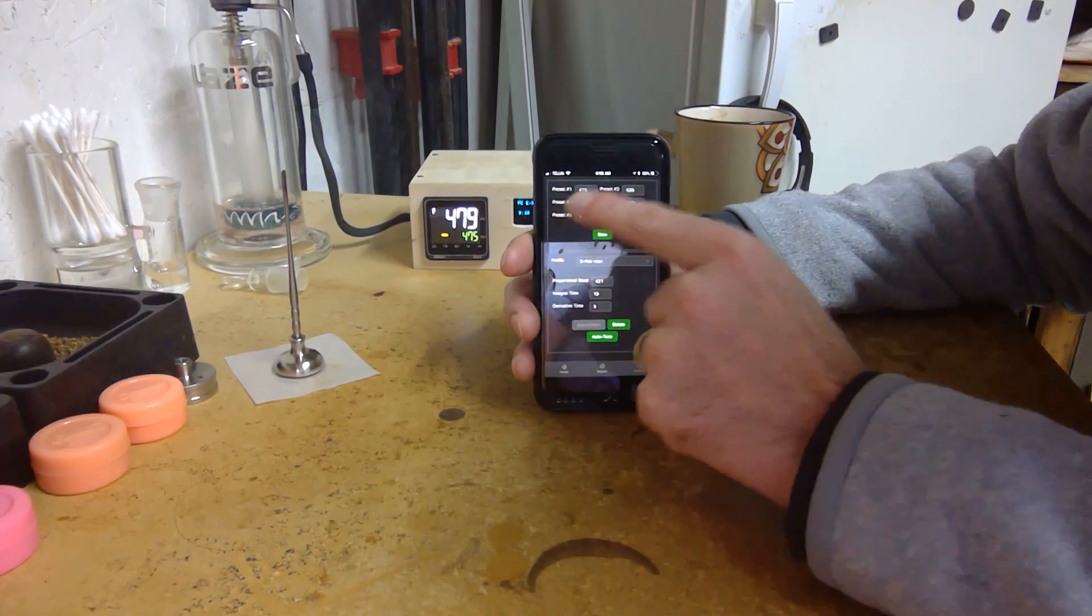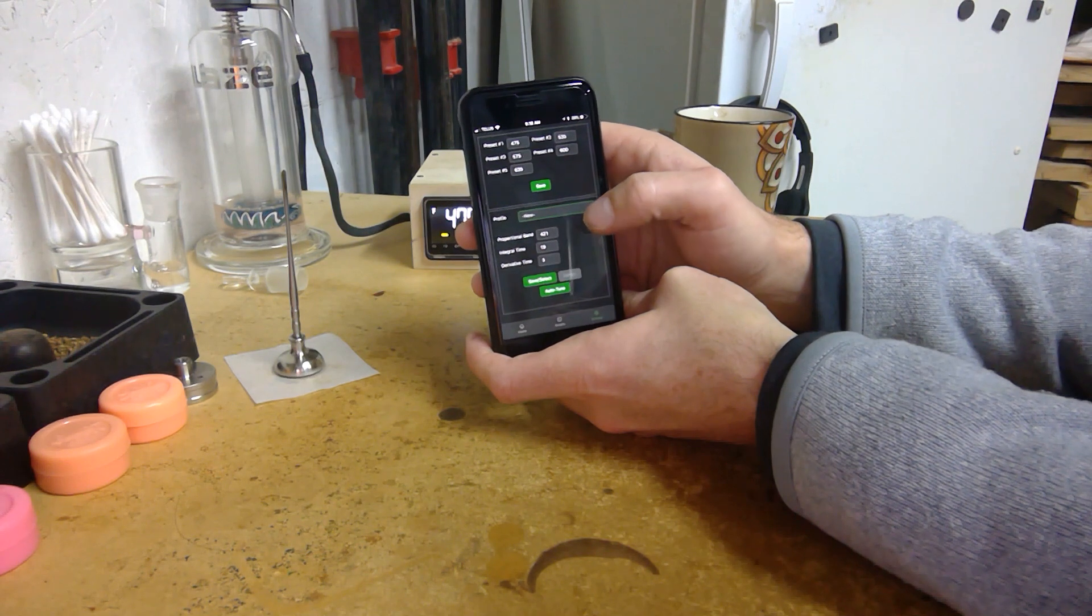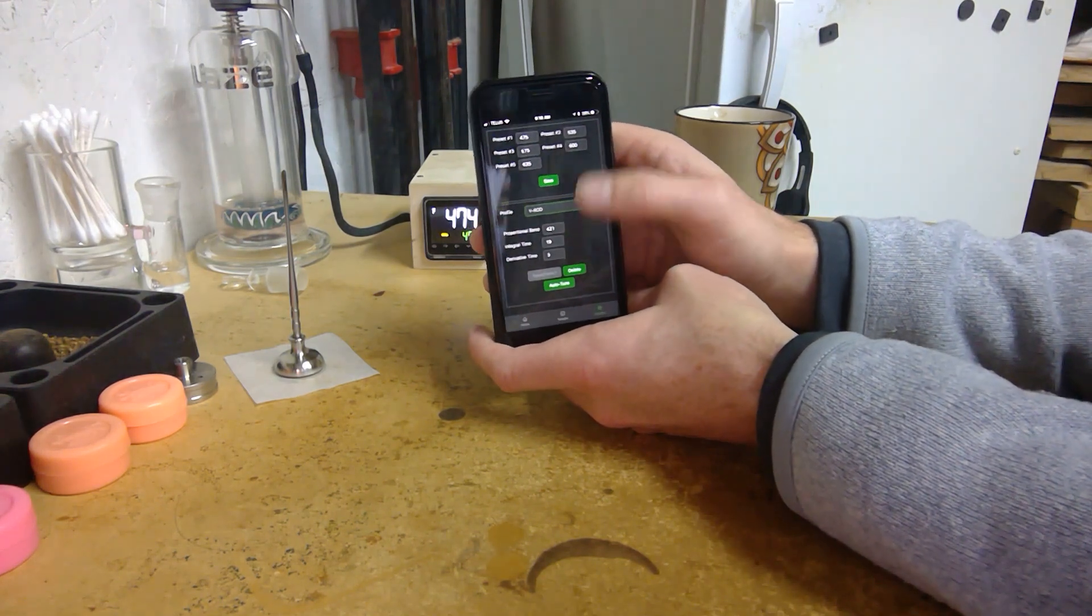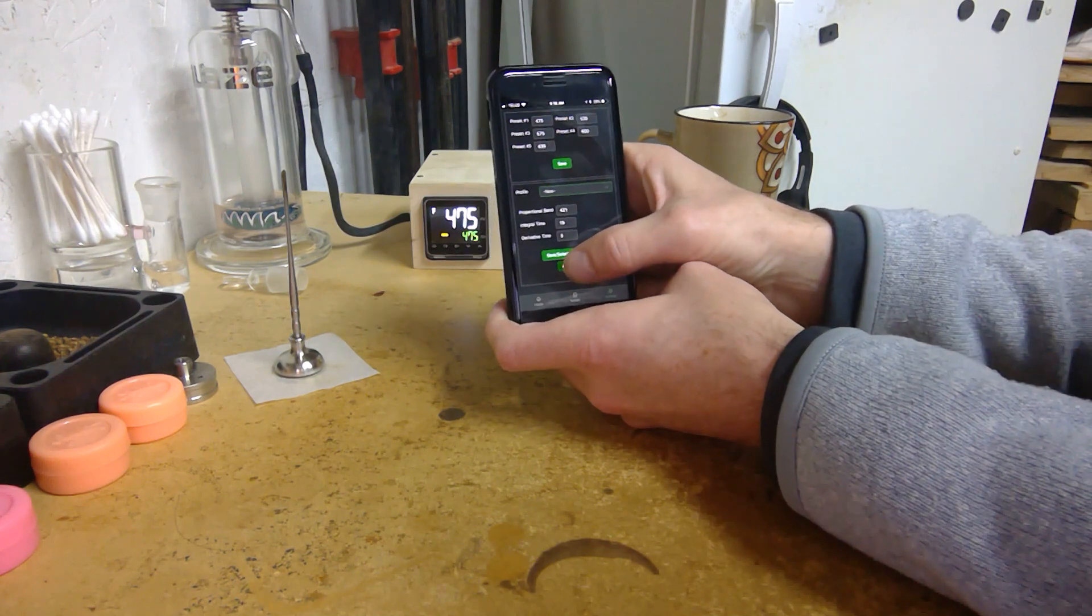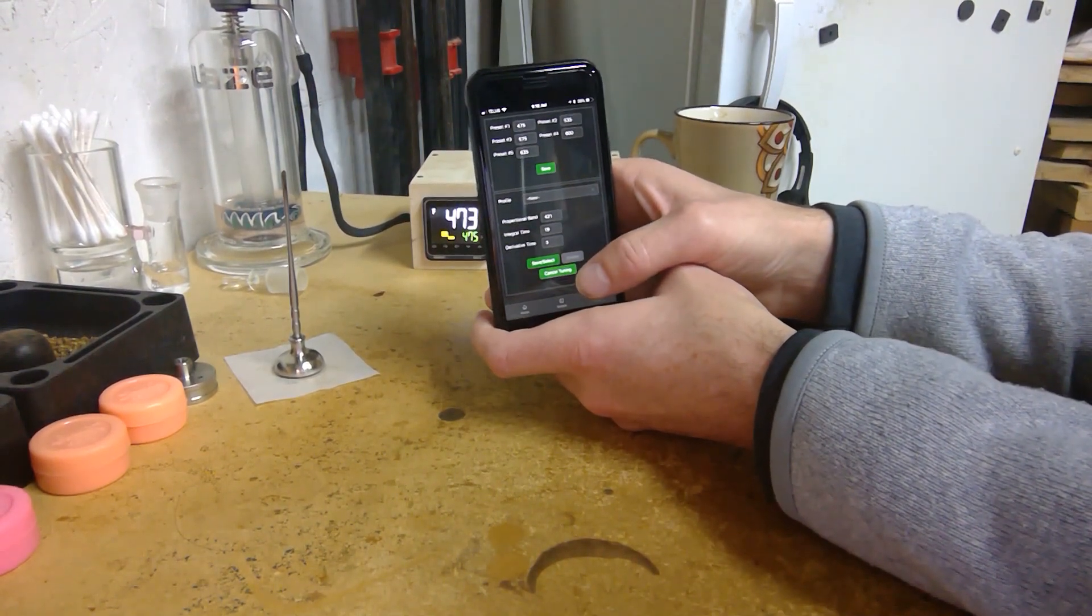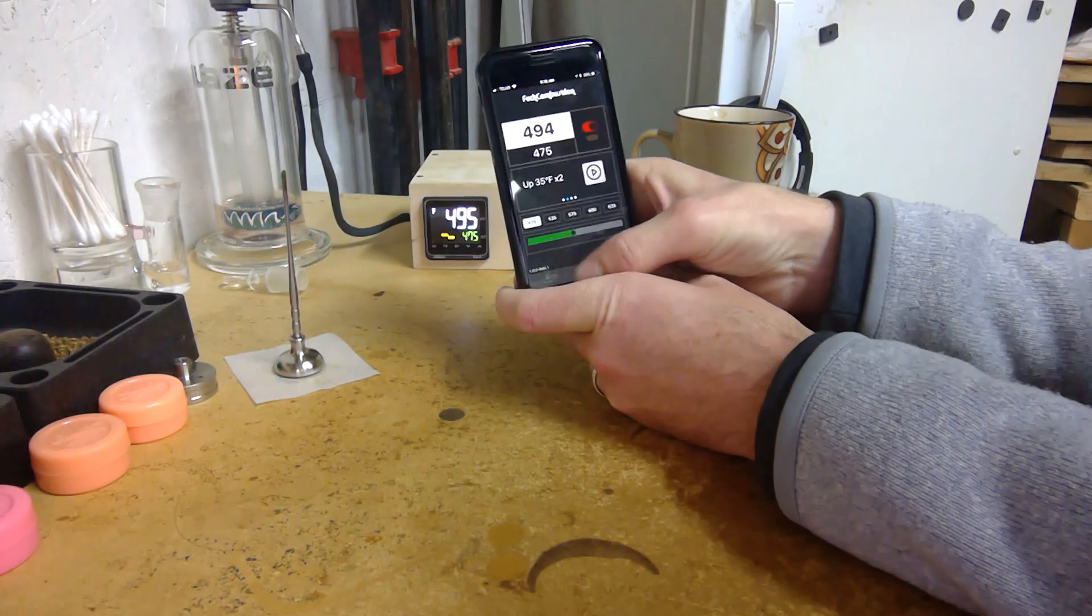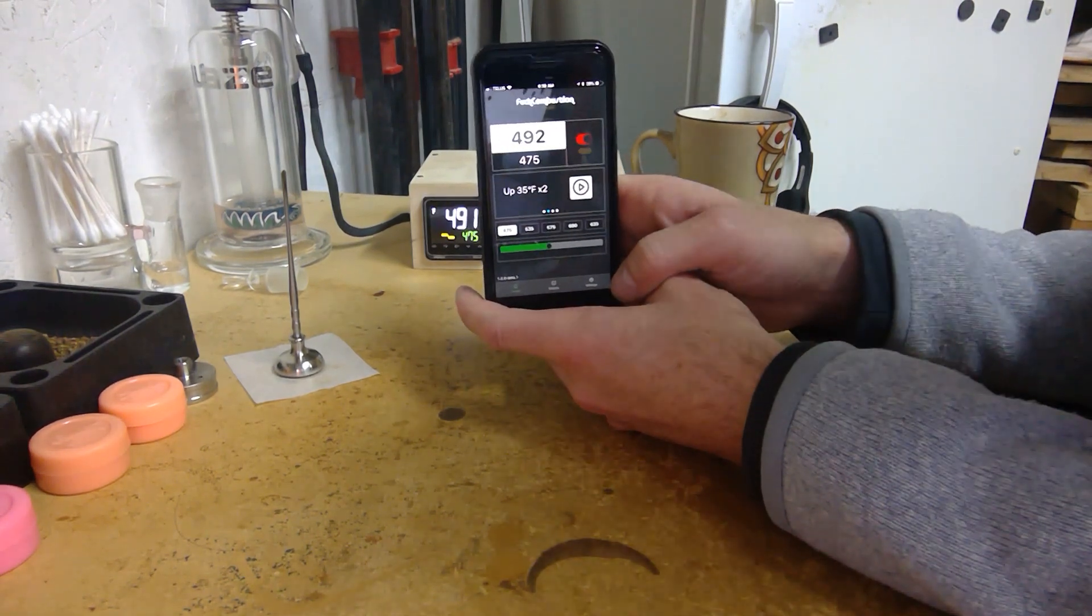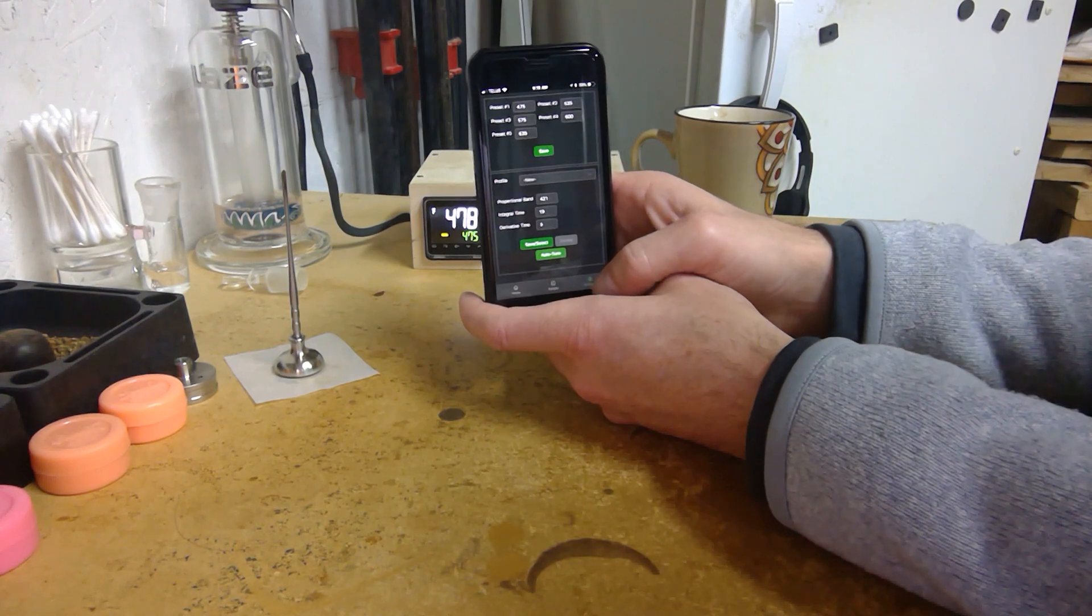From the settings menu, you can enter your presets and save them. You can also pick from saved presets of profiles which you can generate from auto-tuning. My big thumbs don't work great all the time. So you can generate different sets of profiles for your different devices. So for instance, I connect a new device. I go to new where I click auto-tune. Boom. Now it's starting to tune. So when it's done tuning, it'll have updated the PID settings here. I can hit save, put a name beside it, and then those settings get saved to a new profile that I can then pull up at a touch of a button. And as you can see, it's in the process of tuning. It's spiking up the temperature as it does that. The Omron does a wonderful job of auto-tuning. So this is pretty fucking awesome actually. So anyway, I'm going to cancel that because I don't need to tune right now. So there we go. Tuning is cancelled.